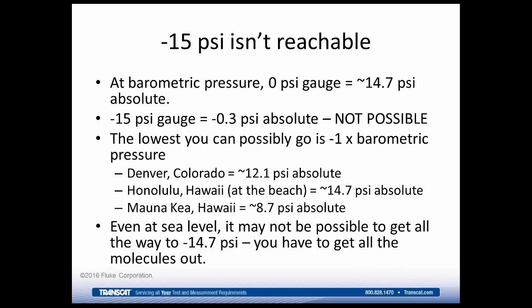So if the auditor or your manager is complaining saying that, hey, this device has a range from negative 14 to 0 or negative 14 to 30, but you only went down to negative 12, tell them, well, we need to do this calibration at the beach. Let me go to the beach, and then we can get it down to negative 14 for you.